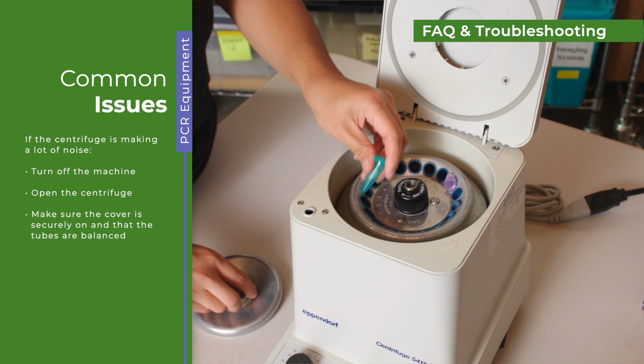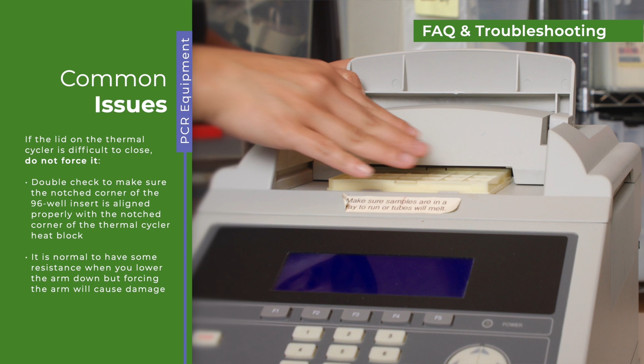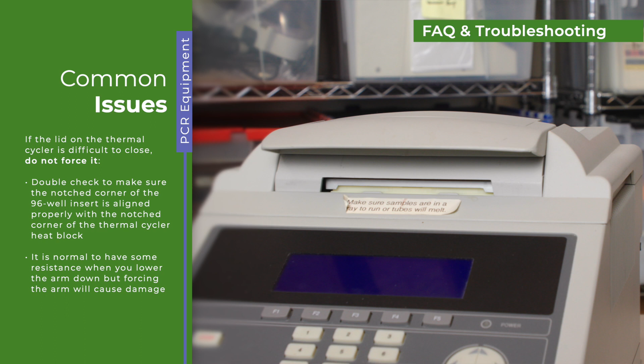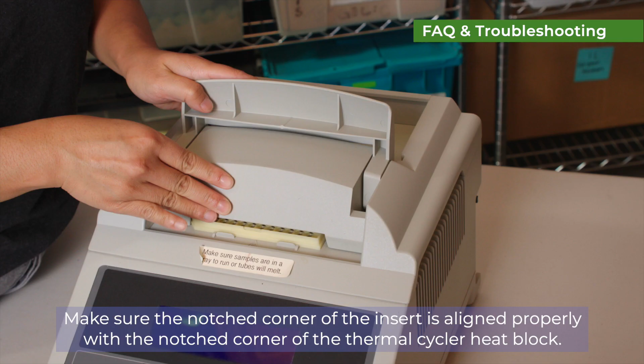If the centrifuge is making a lot of noise, turn off the machine, open the centrifuge, make sure the cover is securely on and that the tubes are balanced. If the lid on the thermocycler is difficult to close, do not force it. Double check to make sure the notched corner of the 96 well insert is aligned properly with the notched corner of the thermocycler heat block. It is normal to have some resistance when you lower the arm down, but forcing the arm will cause damage.